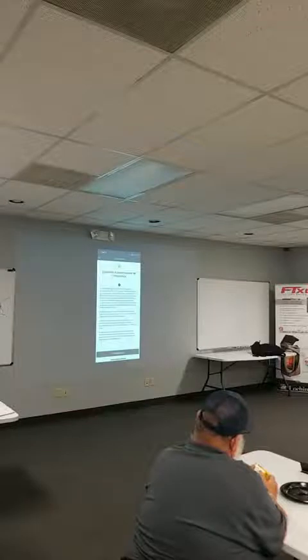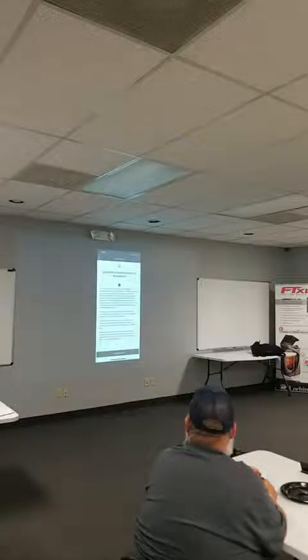Those system flags are typically caused by a wet condenser, a liquid line restriction, or a plugged dryer inside the unit, or a TXV. Right? So verify the condenser is dry. A wet condenser will produce additional evaporative cooling on the liquid. If the condenser was just washed and is taking a long time to dry, use a leaf blower or shop vac to exhaust and blow the water out of the condenser.